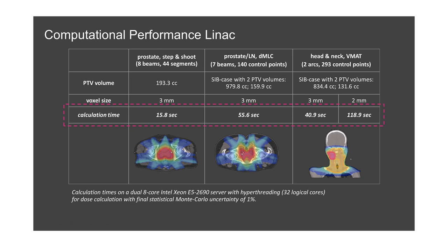This high level of accuracy does not come at the expense of computation time. The slide shows benchmarks for a number of clinical cases with typical clinical voxel sizes on medium-price hardware. It turns out that a clinical case for a normal linear accelerator can be computed in less than a minute, and even the most demanding cases compute in about two minutes. It is fair to say that Symoca computes the dose faster than the linear accelerator needs to deliver that treatment.